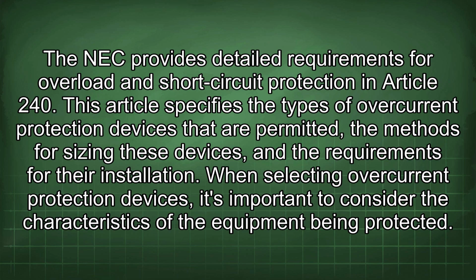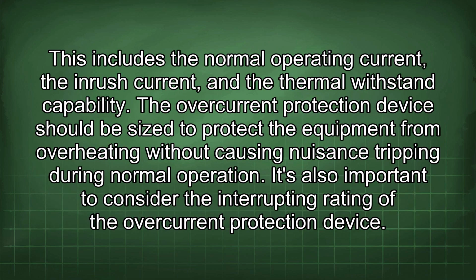This article specifies the types of overcurrent protection devices that are permitted, the methods for sizing these devices, and the requirements for their installation. When selecting overcurrent protection devices, it's important to consider the characteristics of the equipment being protected. This includes the normal operating current, the inrush current, and the thermal withstand capability. The overcurrent protection device should be sized to protect the equipment from overheating without causing nuisance tripping during normal operation.